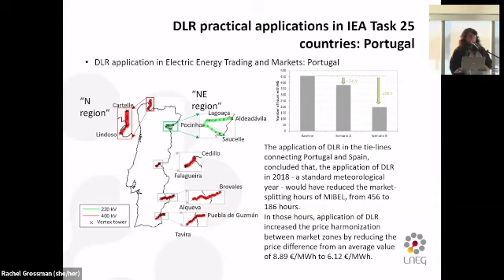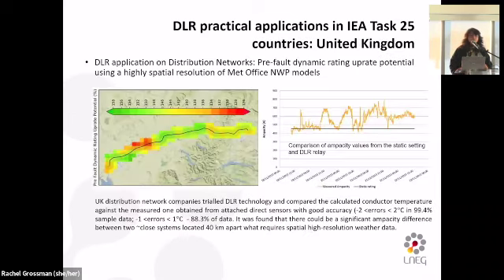So we applied DLR methodologies to the interconnection lines through simulation, and we concluded that the annual periods of market splitting, for a typical year like 2018, would reduce from 456 hours to only 186 hours. In terms of cost, this would mean a reduction from a price difference of 8.89 euros per megawatt hour to 6.12 euros per megawatt hour. So the impact is meaningful in this situation.